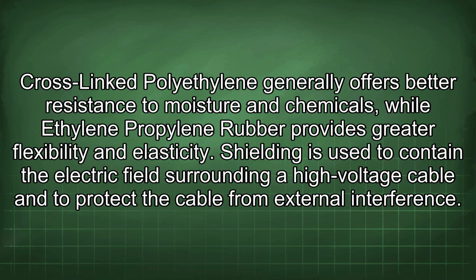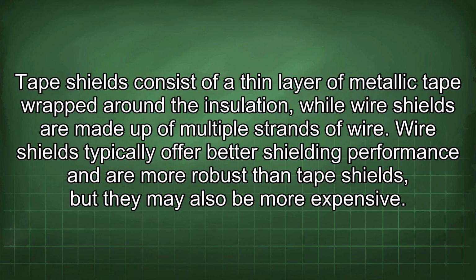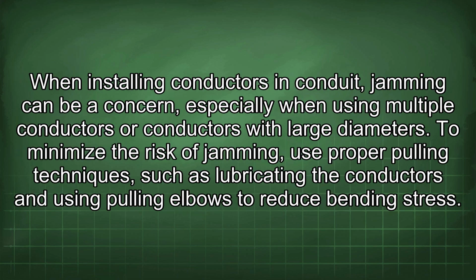Shielding is used to contain the electric field surrounding a high-voltage cable and to protect the cable from external interference. Tape shields consist of a thin layer of metallic tape wrapped around the insulation, while wire shields are made up of multiple strands of wire. Wire shields typically offer better shielding performance and are more robust than tape shields, but they may also be more expensive.